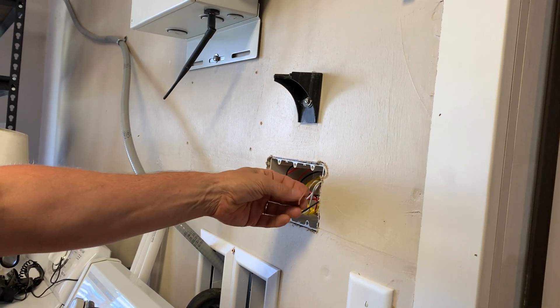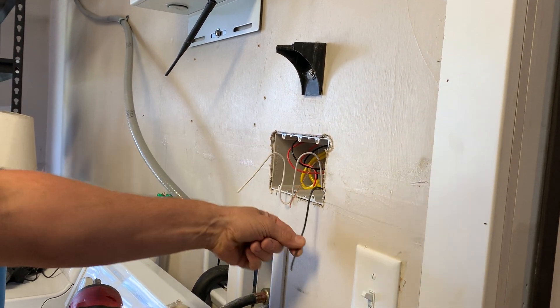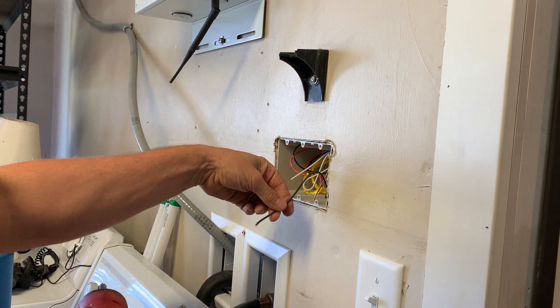If you have an older home with no grounds and you're already doing a kitchen and bathroom remodel but not updating the wiring, that doesn't make sense to me. What does it mean to have a ground wire? An EGC — Equipment Grounding Conductor — inside of NM cable (non-metallic, what you guys call Romex, which is a slang term you won't find in the code book) — that NM cable has its ground. You may have your ungrounded conductor (hot), your grounded conductor (neutral), but you may not have your grounding conductor — the bare copper.